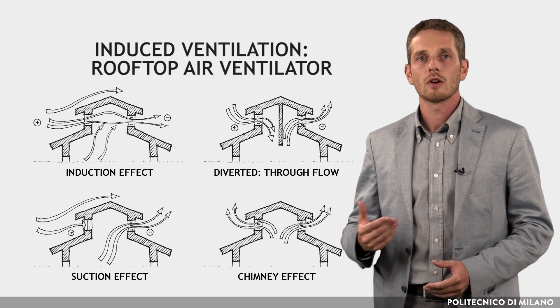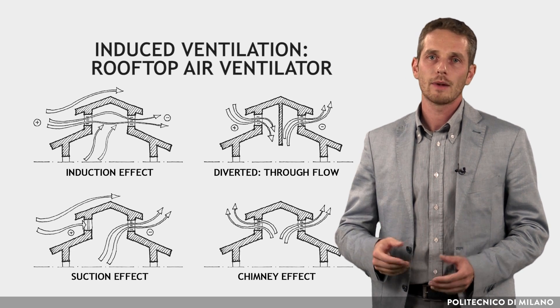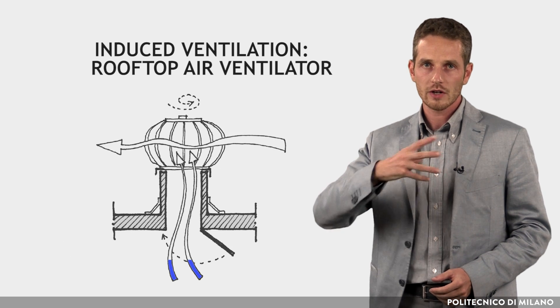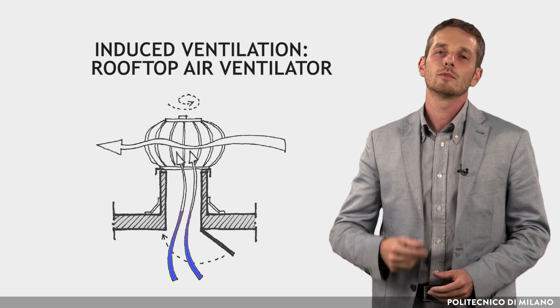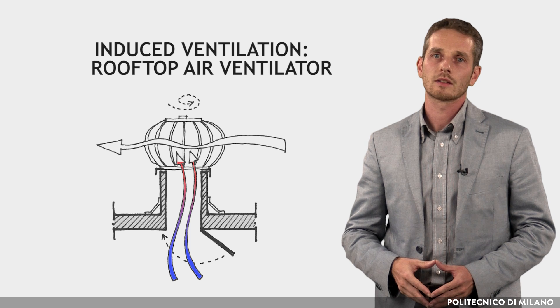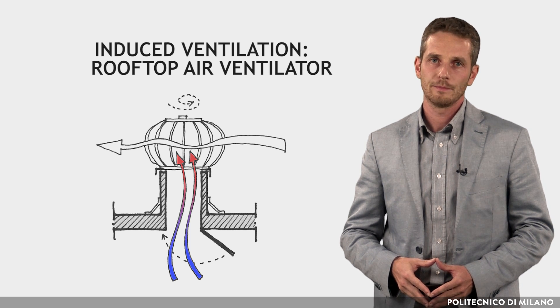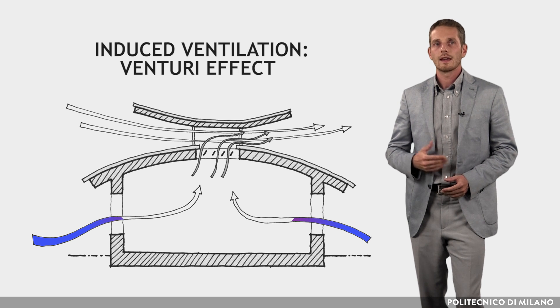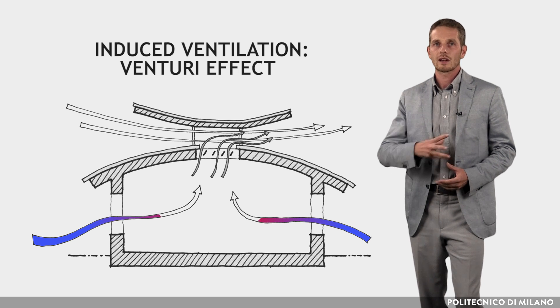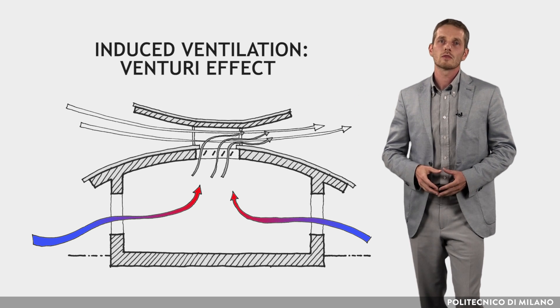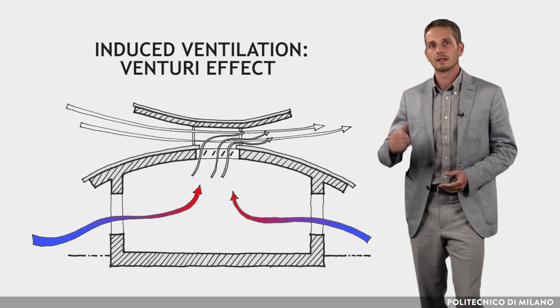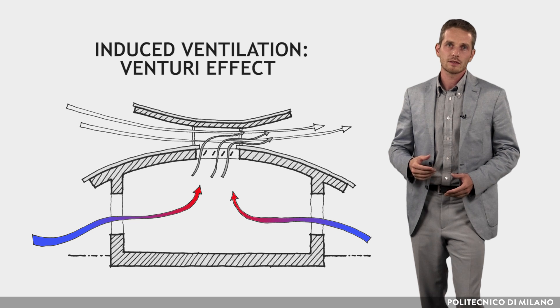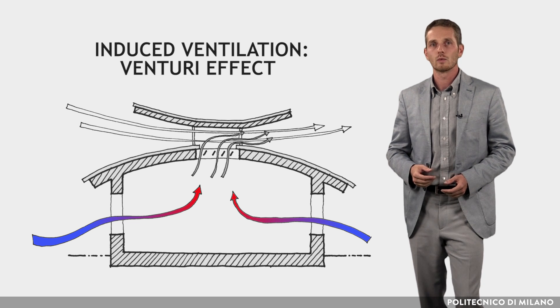The second way exploits wind velocity either by channeling the airflow inside or by creating depression with a rotating device moved by wind to extract air from the building. The third way exploits the venturi effect, where air is extracted from the building because of the low pressure created by the wind on top of a shaft. In windy areas it could be an effective alternative to wind catchers.